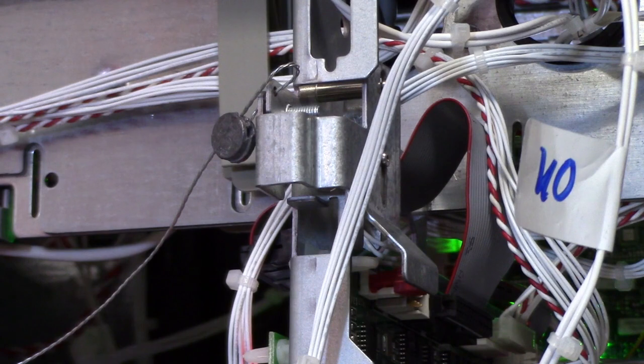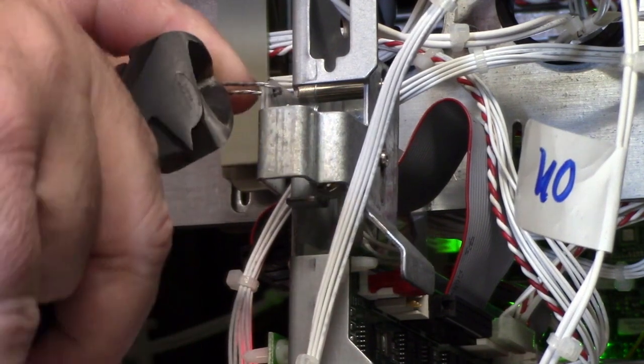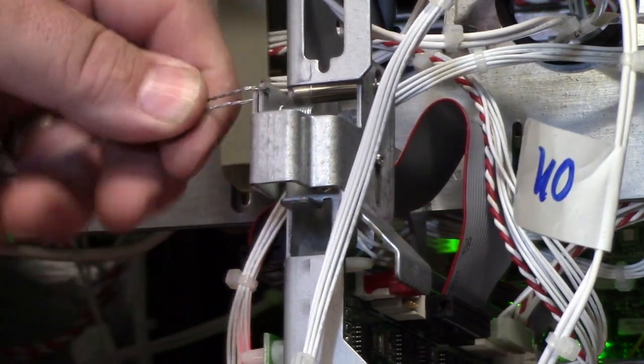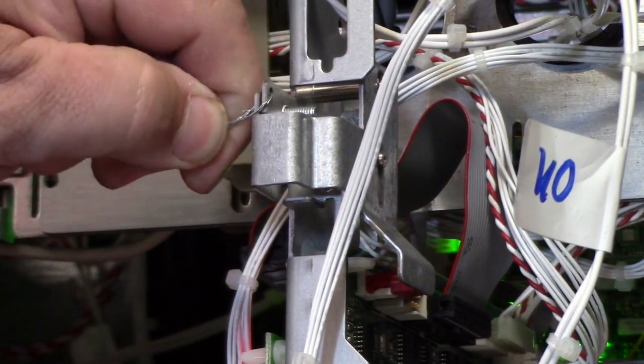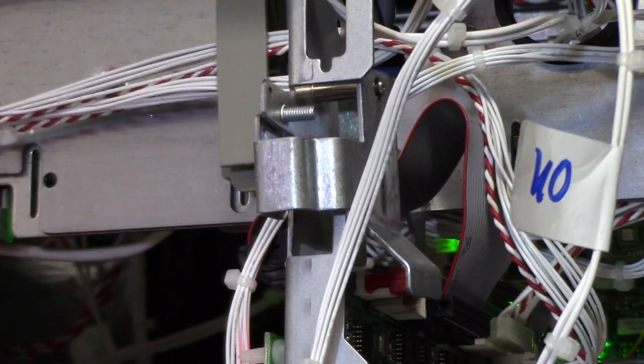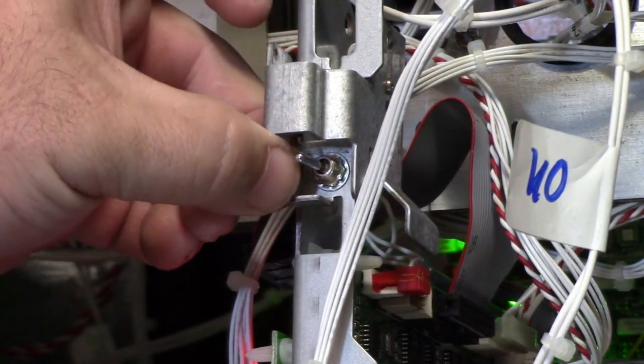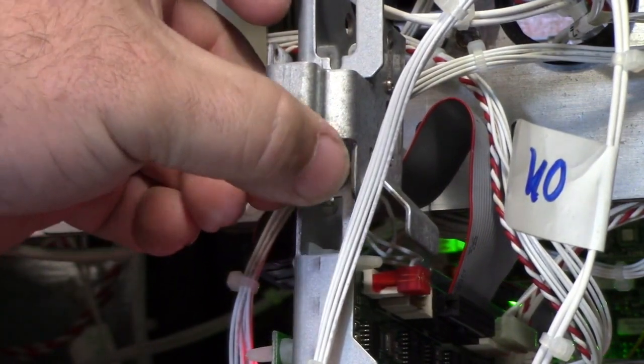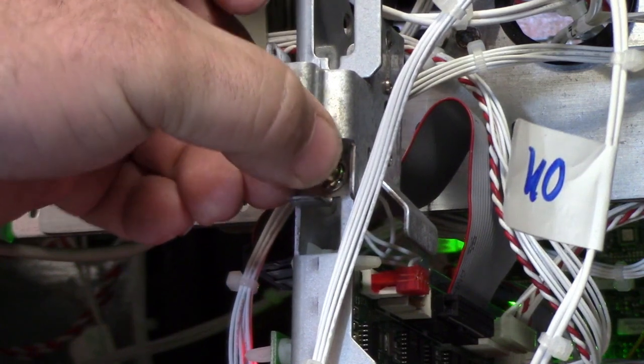After we've pumped to 0, we're going to open the door of the pump. We cut off the old lead seal with a pair of side cutters and remove that old lead seal. Once the seal is removed, we flip the switch to the right. You hear the double beep, flip it back.